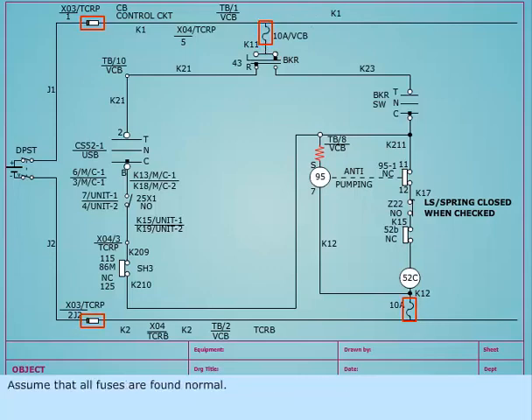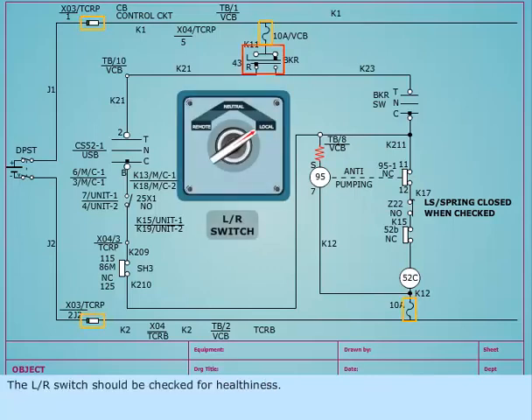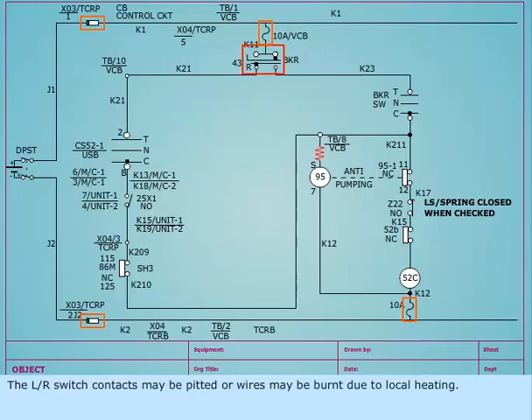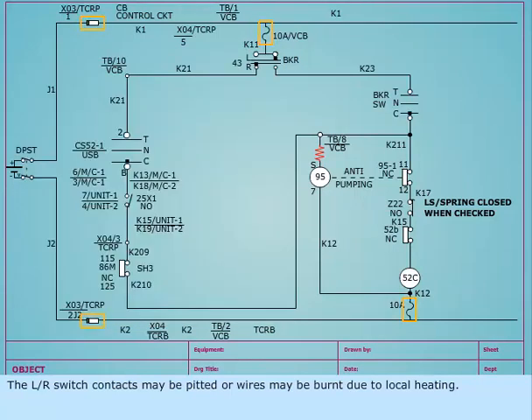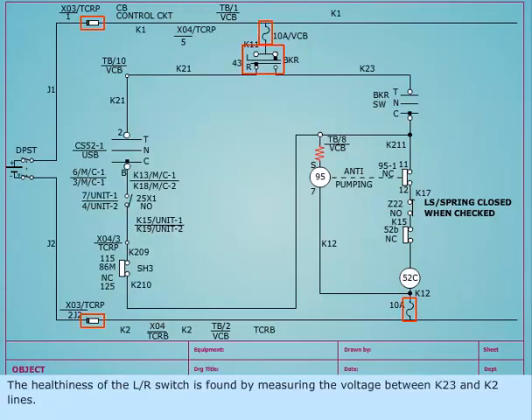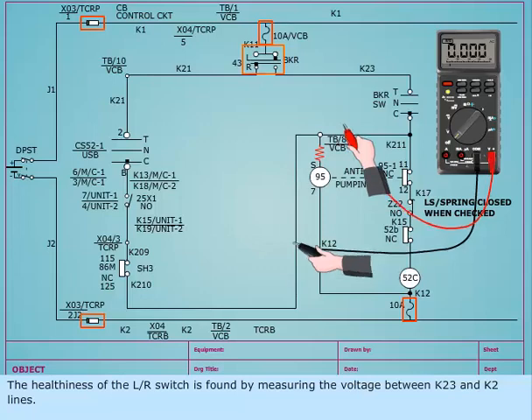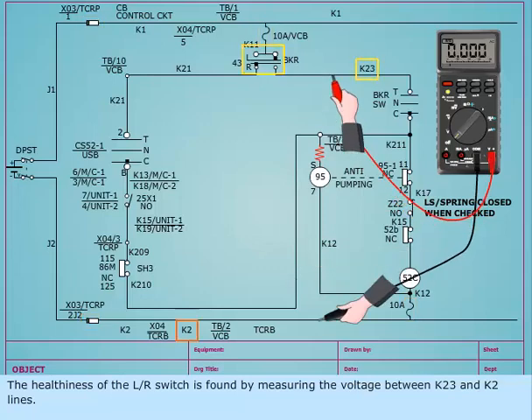Assume that all fuses are found normal. The L/R switch should be checked for healthiness. The L/R switch contacts may be pitted or wires may be burned due to local heating. The healthiness of the L/R switch is found by measuring the voltage between K23 and K2 lines.